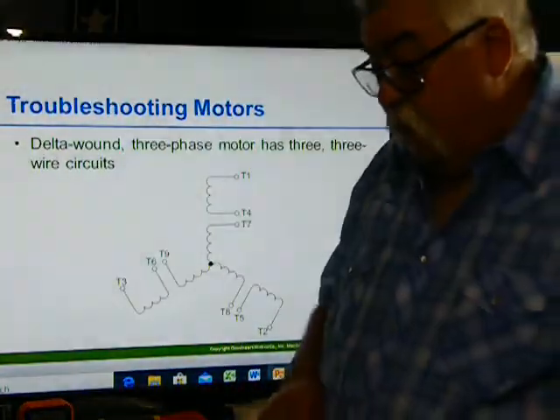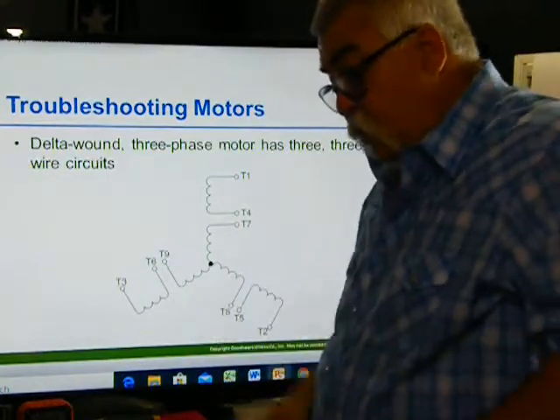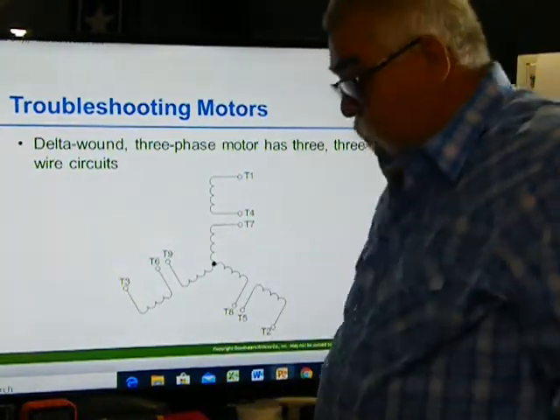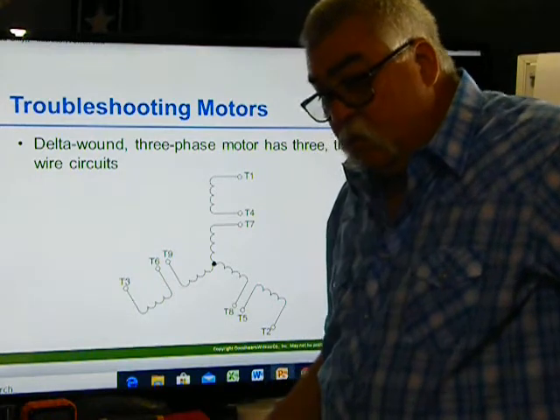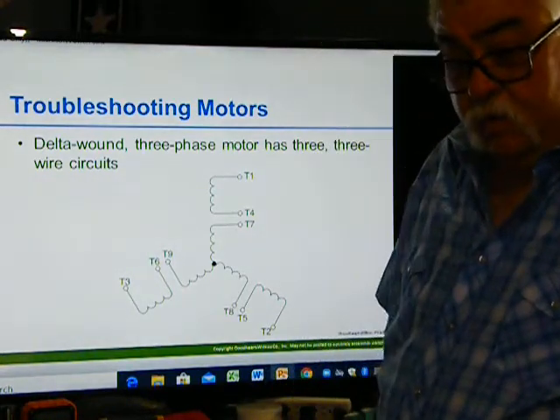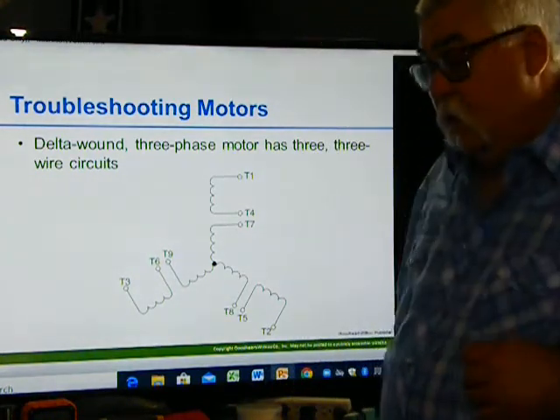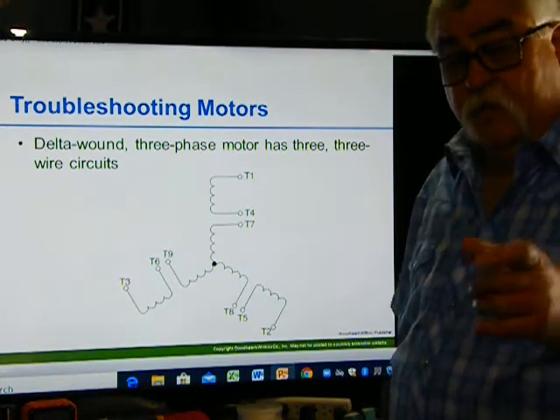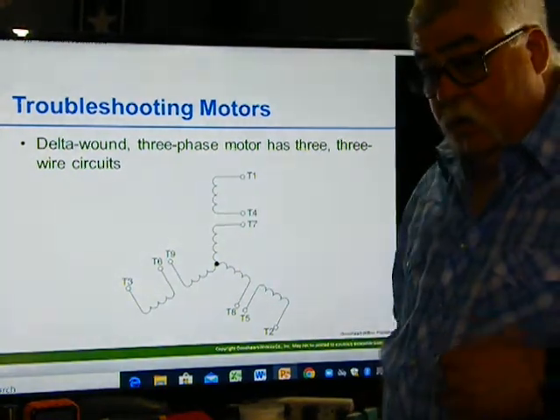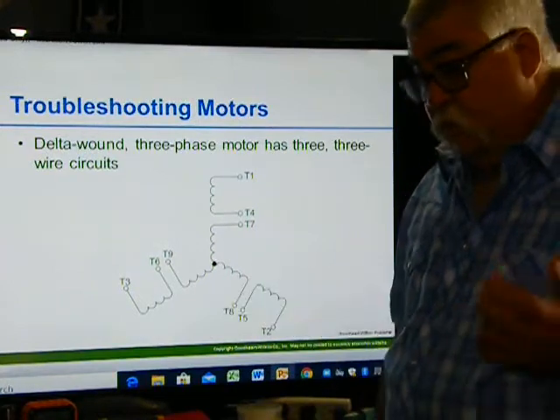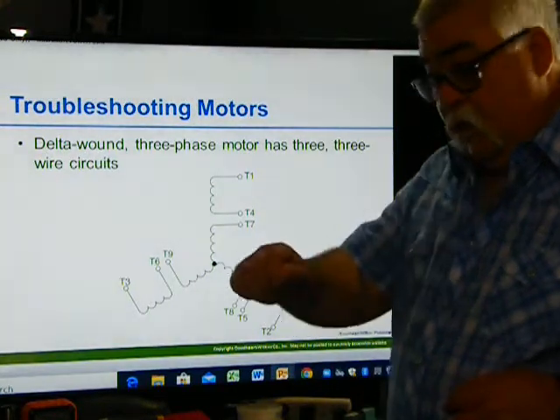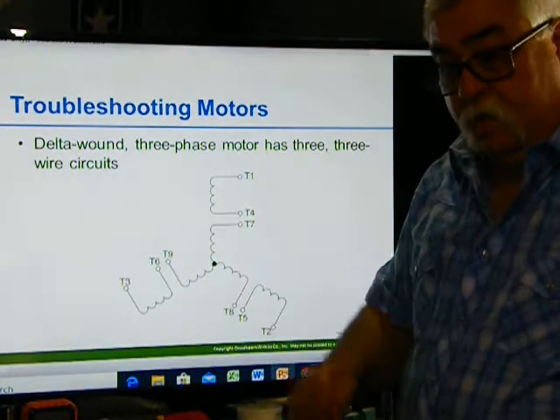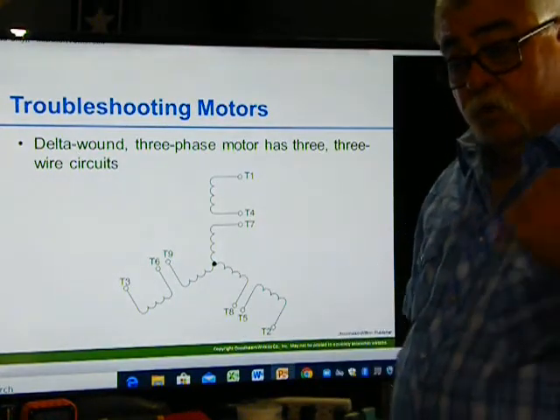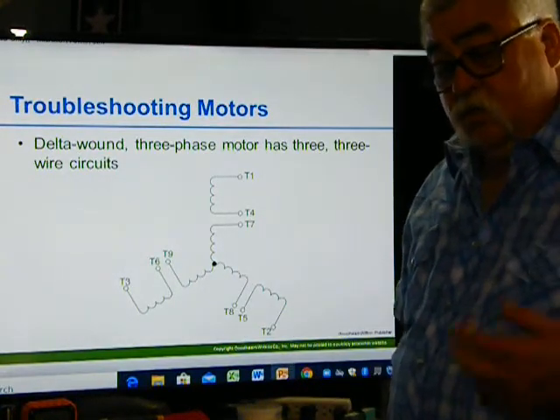And on page 256, it gives you an idea of how you would test, how you would find these windings. For the most part, most motors, even when they're rebuilt, they do put labels on them, so you can know what it said. They may not have a nameplate. We've had them where they come in, the nameplate's gone, 15 horsepower, 20 horsepower, 40 horsepower, and it's written down with a Sharpie on the top. But all the wires are labeled, so you know which is T1, T2, T3. So each one is labeled.